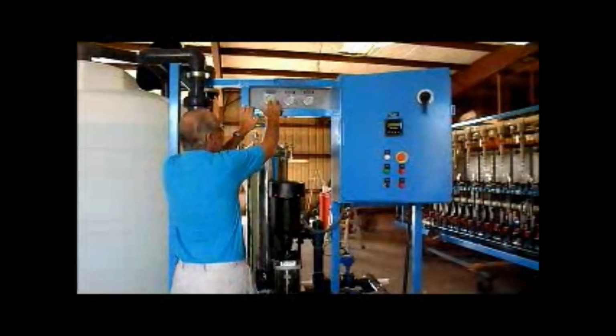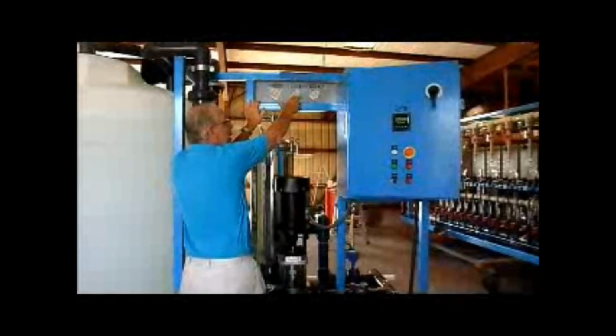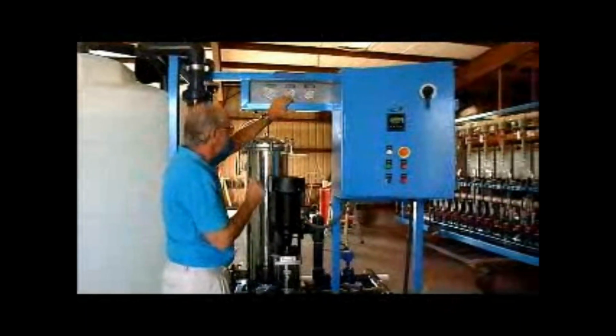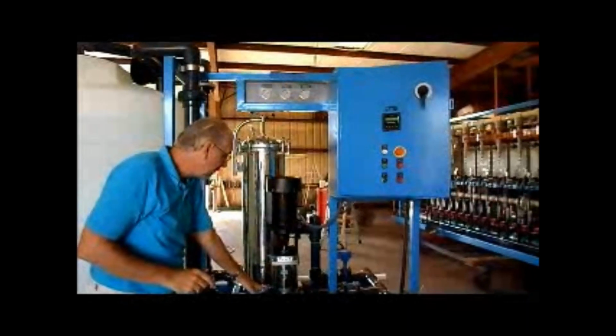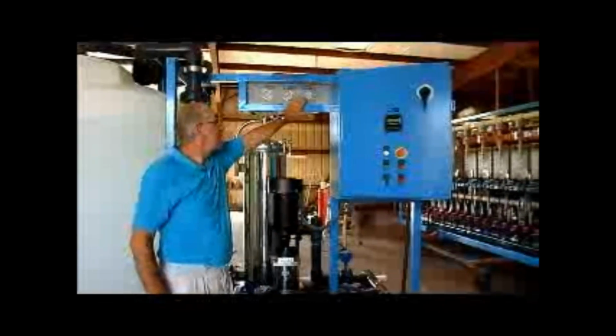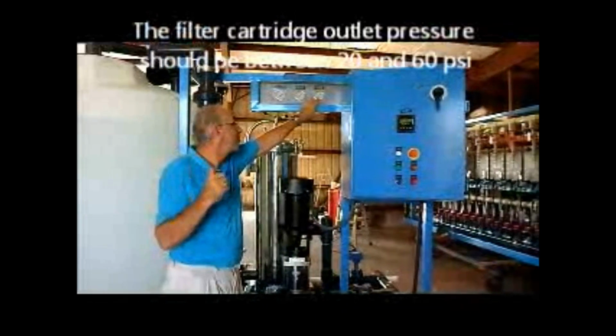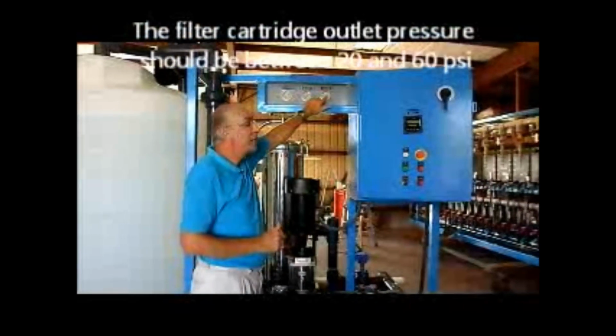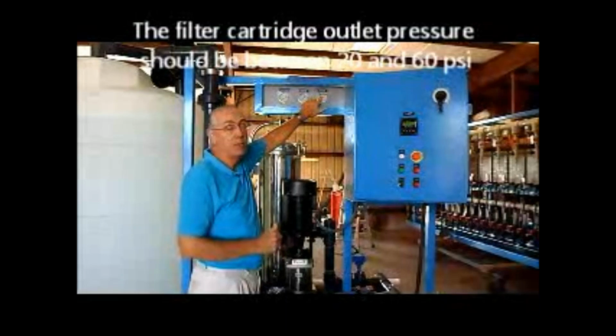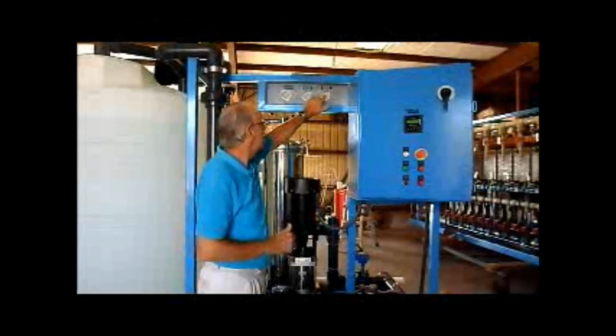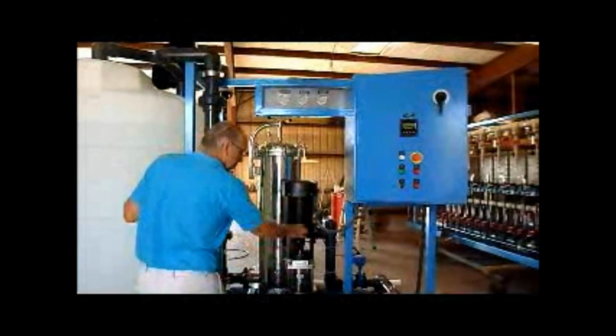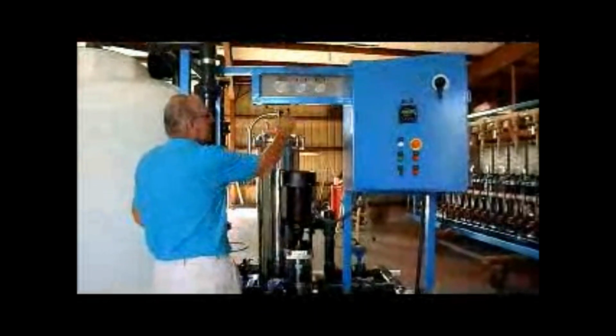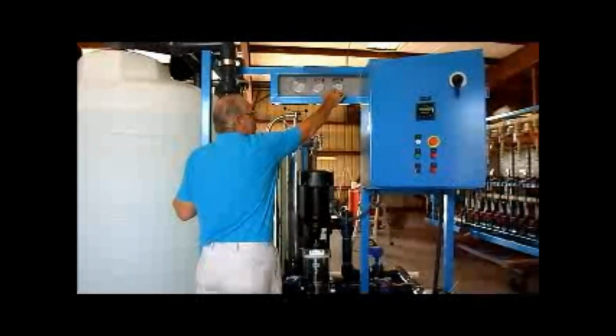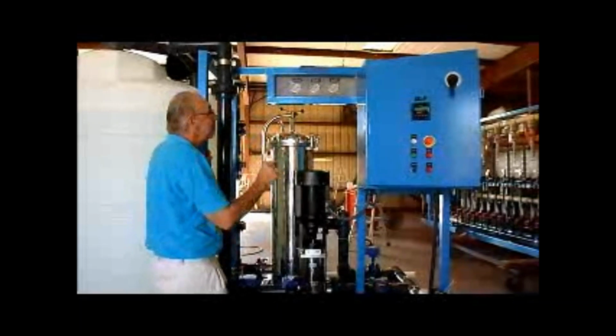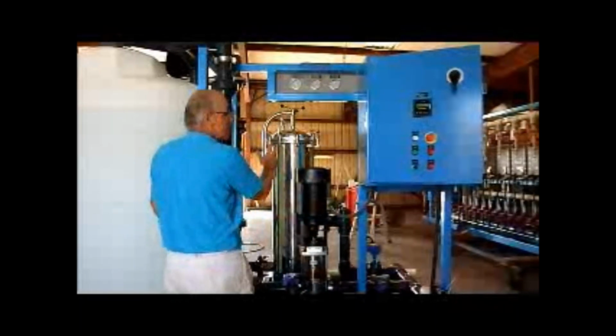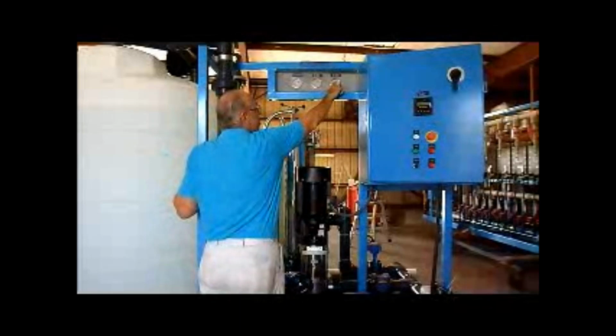If there's a huge drop here between your pump discharge pressure and your cartridge filter pressure, you can adjust these valves. The important thing is that this pressure going into the RO membrane should be between 20 and 60 psi, preferably more between 40 and 60 psi. If for some reason you have these valves adjusted or the cartridge filter is clogged and the pressure drops too low, the cleaning will not be as effective. So you have to adjust these valves and use clean enough cartridges that you can keep this pressure here between 40 and 60.